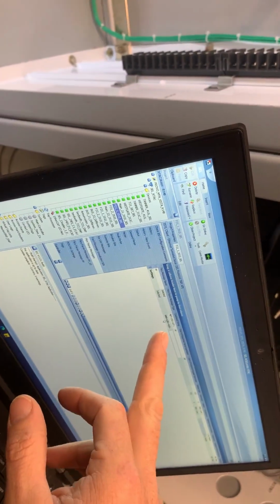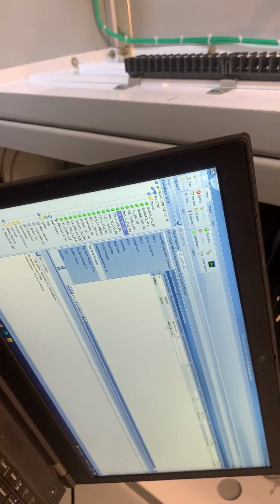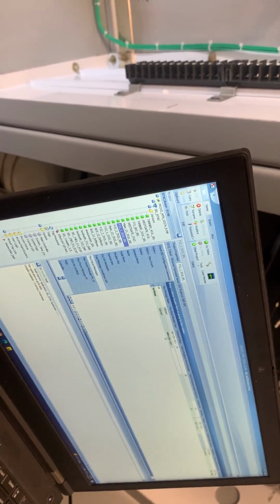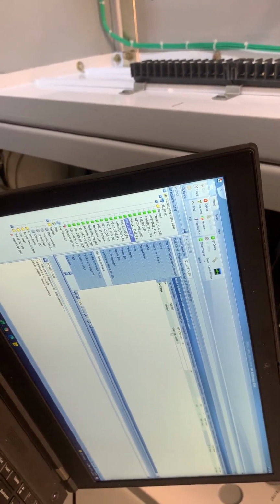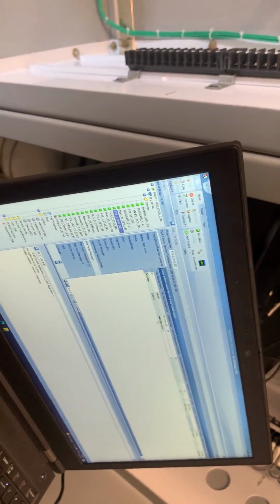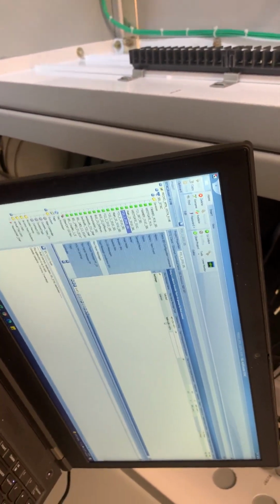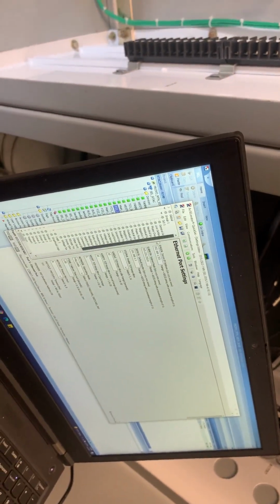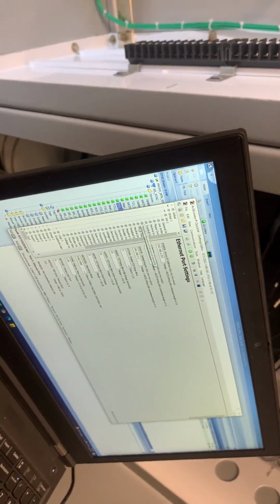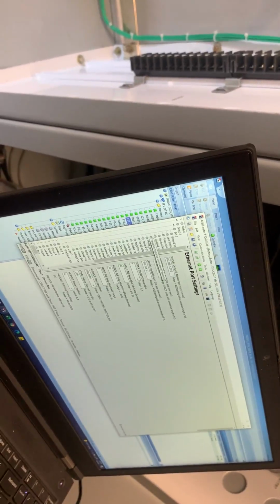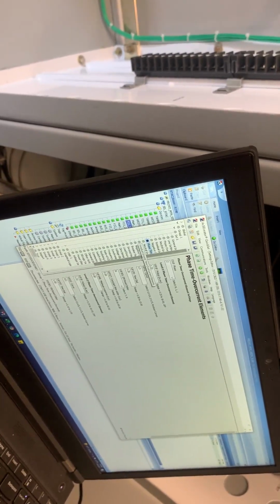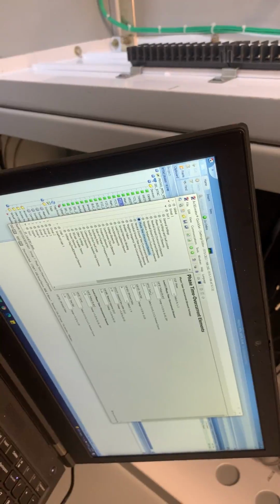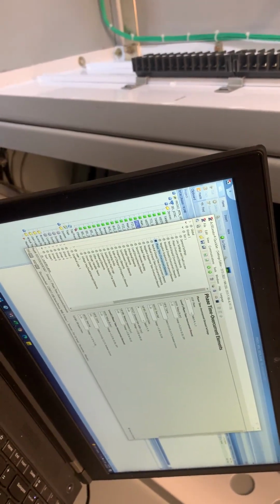Now, this is the tricky part. I have to know what I'm looking for in the relay, and I've got to figure out a word that it can look for that's going to be unique and only shows up once. Well, in this case, you want to know the pickup setting. So I'm going to go all the way down to the exact setting I'm looking for, which in this case you wanted the phase time overcurrent, right? So I'm going to tell it to go look for 51P1P.